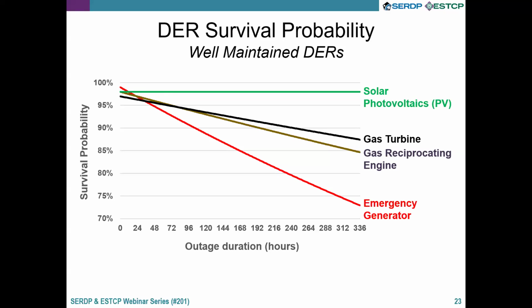What's plotted here is survival probability versus outage duration, from 1 hour out to 2 weeks. The red line at the bottom is the emergency generator. This comes as a surprise to people who don't work in the field: emergency generators are extremely reliable if you're worried about a few hours. Their availability is quite high and they rarely fail within the first few hours. But if you try to run an emergency generator for 2 weeks, on average under 75% of them will survive.